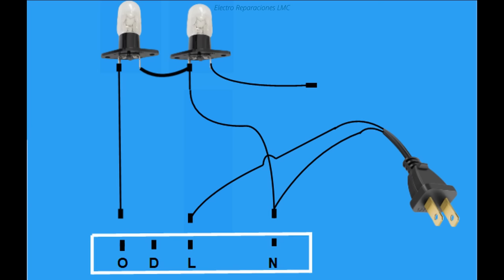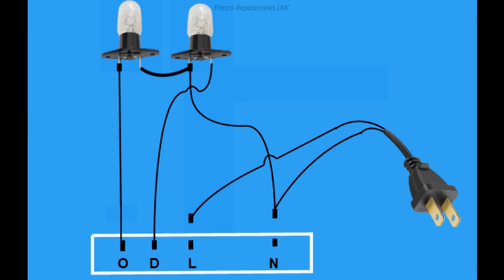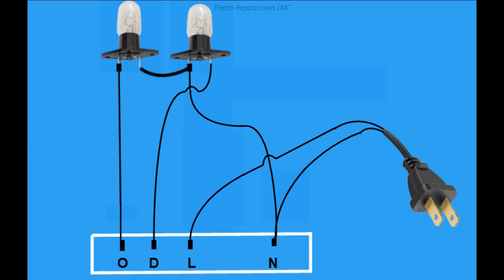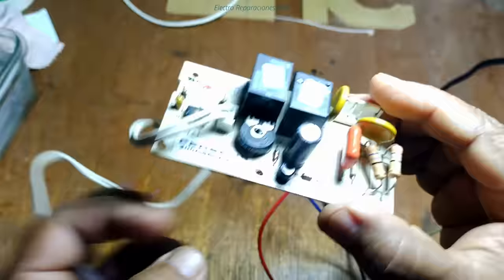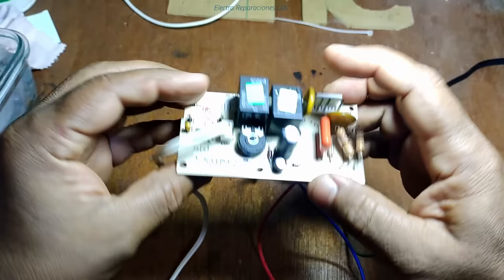El cable de alimentación tiene dos conductores: uno de ellos va conectado a la ramificación del puente entre los dos bombillos. El otro conductor del cable de alimentación queda libre a través de un conector bastón, y al último terminal del bombillo de la derecha le ponemos otro cablecito con conectores bastón. La tarjeta tiene un conector con cuatro terminales: N de neutro, L de línea o fase, D para la resistencia de deshielo y O que conecta al compresor.